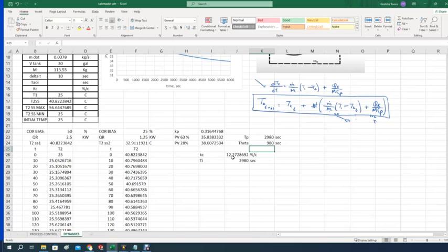I like to, because I know that it's going to be tuned a little bit further as I operate the process control. Like for example, right now I'm using this equation that shows there. What it is: 1 over Kp times tau p over theta, the process time divided by the dead time, elevated to the 1.22. All right, that's the Kc value.